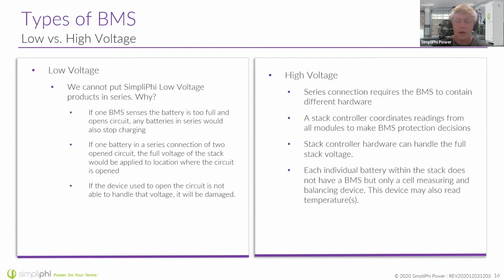If you've got two batteries in series, say 100 volts from two 48-volt batteries in series, and one of the batteries gets too full and opens the circuit, it's going to slam all 100 volts from that circuit onto the point where the BMS opened. That's 100 volts right across that BMS, and in many cases the BMS is just not designed with hardware components to handle that 100 volts.